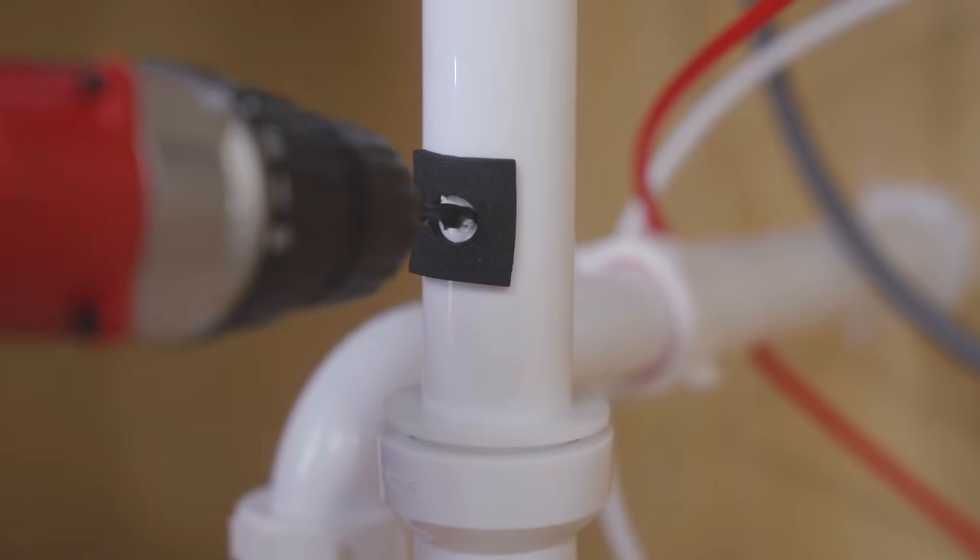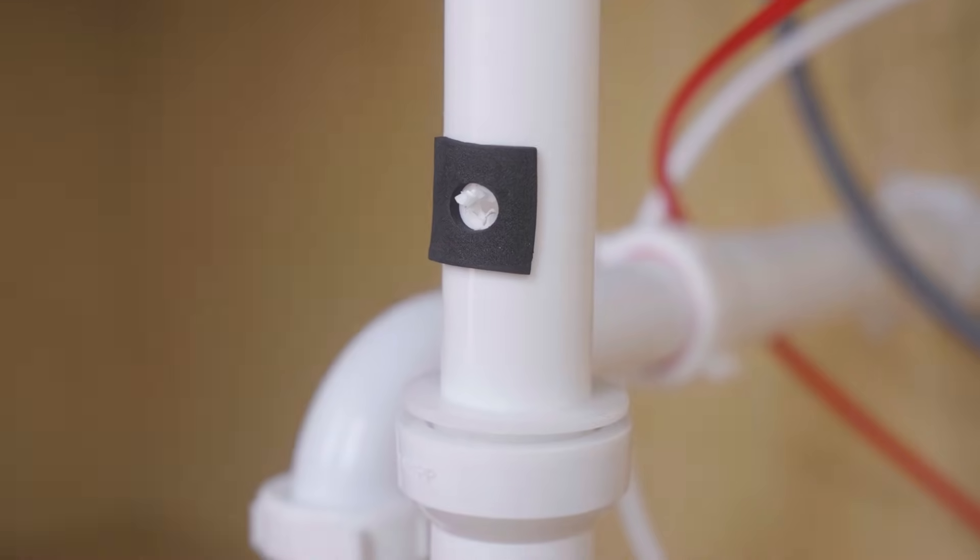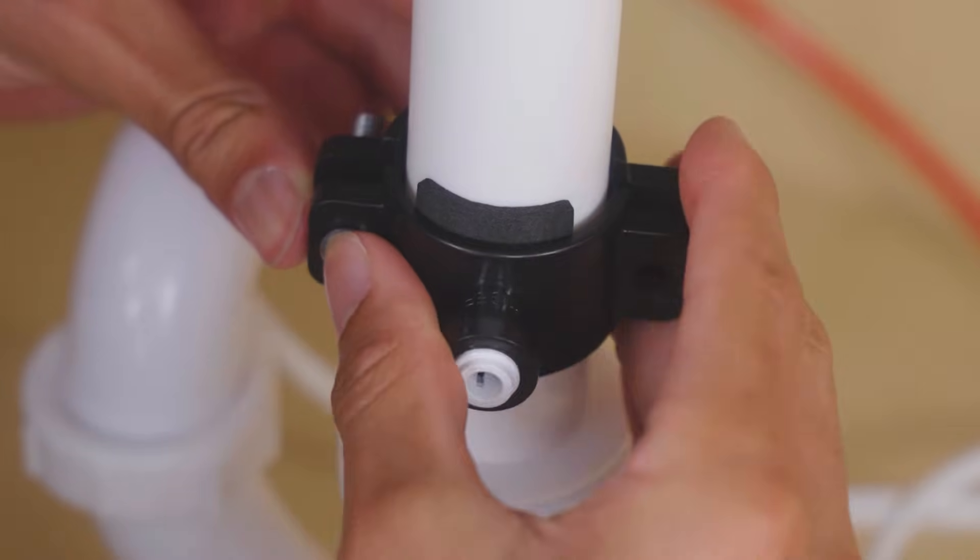Drill a quarter-inch hole in the drain pipe, horizontal or vertical, above the trap. Clamp on the drain saddle and line it up with the hole. Insert the black tubing.